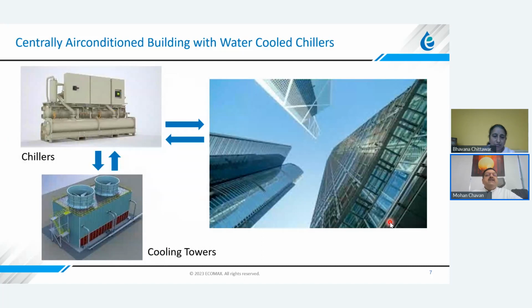In a centrally air-conditioned building, mainly in weather like India's, we have mostly water-cooled chillers, because water-cooled chillers are efficient, okay? That's where, in most places, you'll find water-cooled chillers installed, and if there are water-cooled chillers, we have cooling towers attached to them, right? So the combination of these two will treat the air, and that's where we get the cooling in the buildings. And we have condensers here in the chillers.